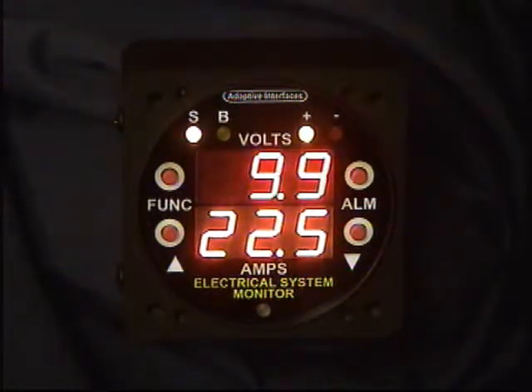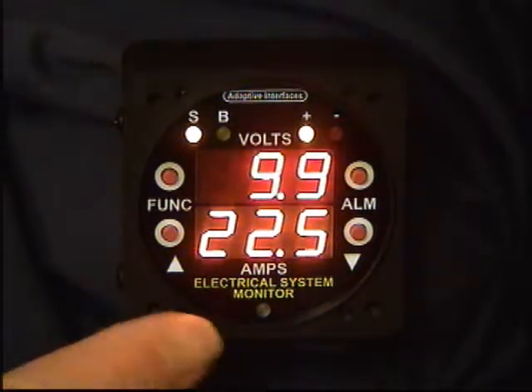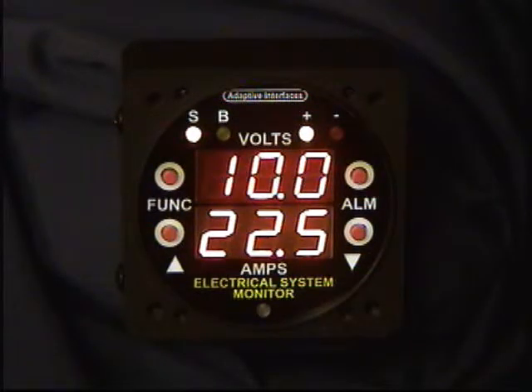In order to turn off this alarm condition, in the normal operating mode of the instrument, you use the alarm button. By pressing this, you turn off your alarm condition, and it will stay off for 2 minutes. But again, after 2 minutes, if an alarm condition still exists, the instrument will go back to flashing and indicating an alarm. Basically, the 2 minutes just gives you some time to work out your problems and not be distracted by the instrument. But again, we want the instrument to do its job and let you know that you do have a potential electrical problem. If the alarm condition goes away, if we go back to a normal voltage, the instrument should operate perfectly, and you can just go on your way.